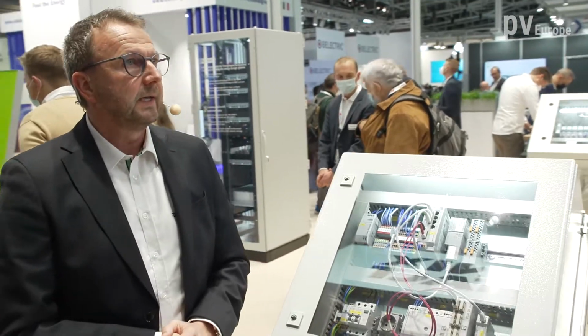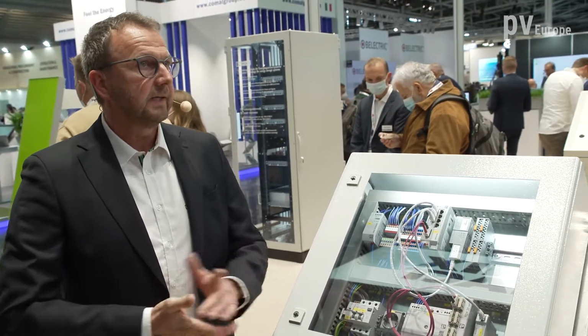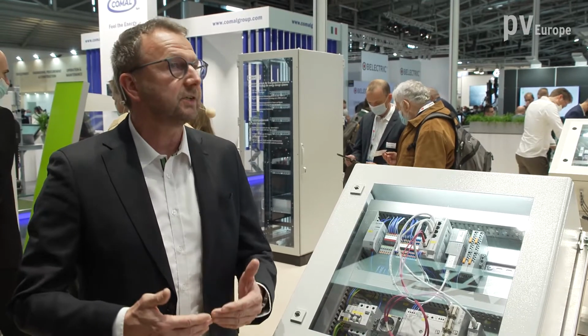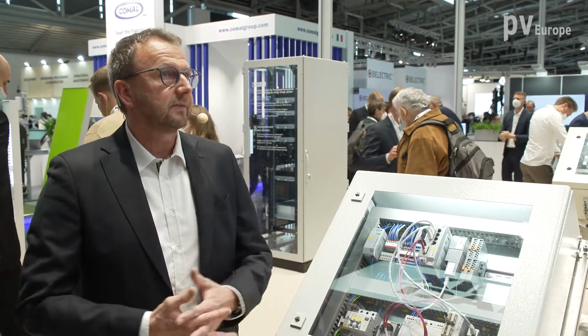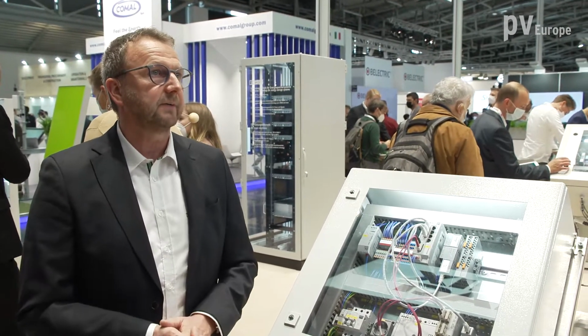What other features does the device offer? We added other optimizations in the last 1.5 years, like integrating a test mode. That means you can test your power control unit at your desk, at home, in your laboratory or workbench, and then shift it to the PV plant for installation and commissioning. For this commissioning, we integrated a test mode so you can preset some values from the grid operator, because normally in pre-commissioning you don't have connection to the grid operator. Therefore you can set some set points and test the behavior directly on site.